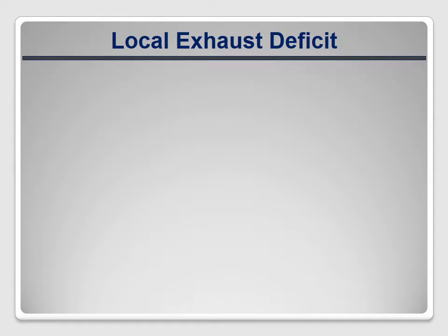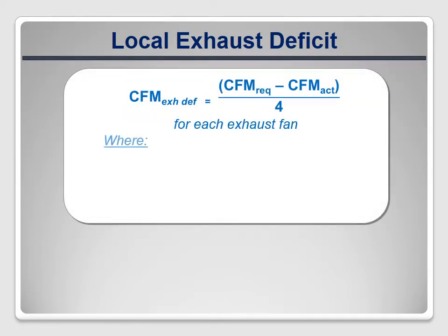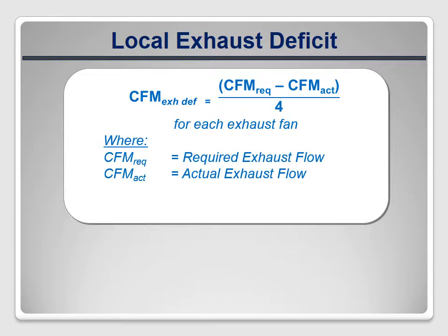The local exhaust deficit calculation compares the actual exhaust flow rate to the rates required for new construction in ASHRAE 62.2. The deficit is one-fourth of the difference between the two — presumably because we don't expect local exhaust fans to run all the time; they're typically intermittently operated. In addition, a credit of 20 CFM per room is allowed if one or more operable windows are present in that room to provide additional ventilation as needed.